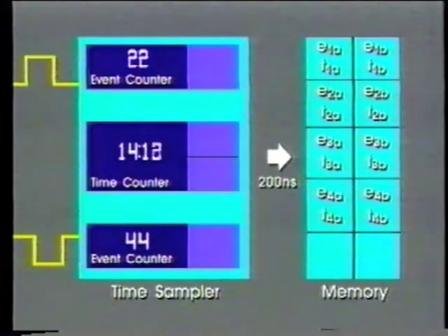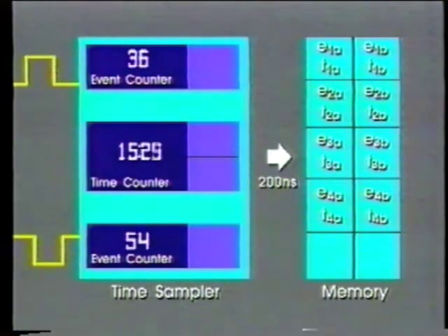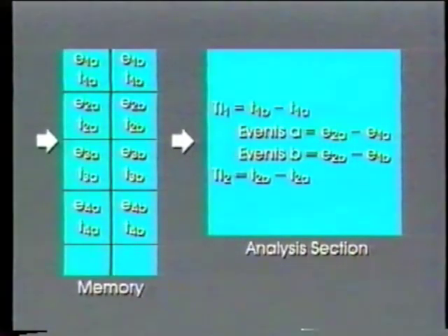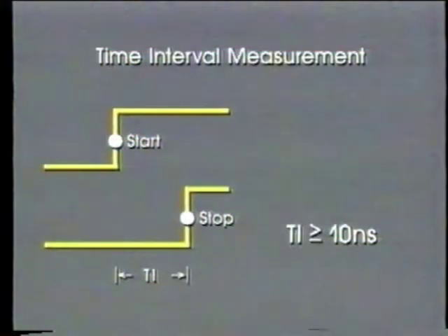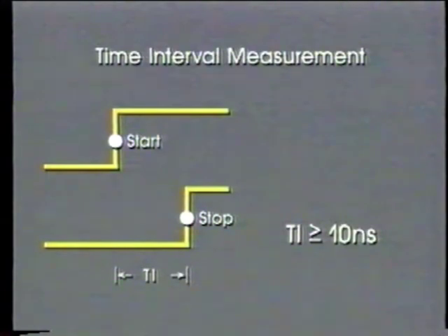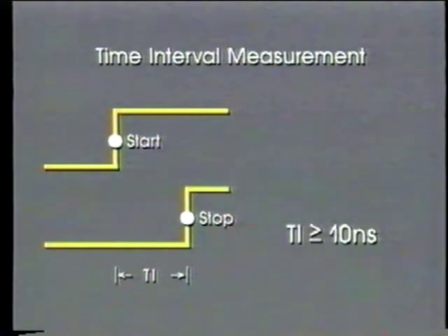If events happen faster than this, they will be counted but not timed. The calculation shows the time interval measurements and notes the events that were not time tagged on each channel. With time interval measurements, you always measure from a start to a stop. The result is always positive, and the minimum interval is 10 nanoseconds.